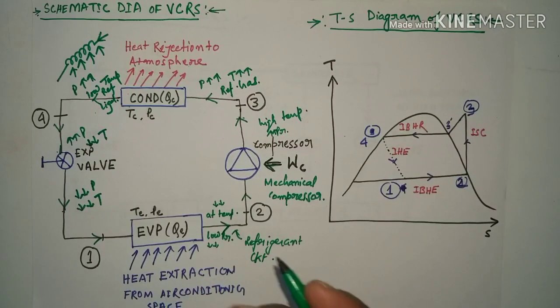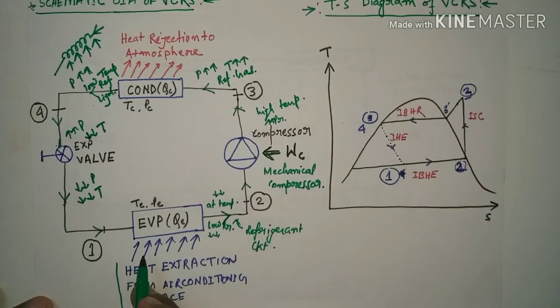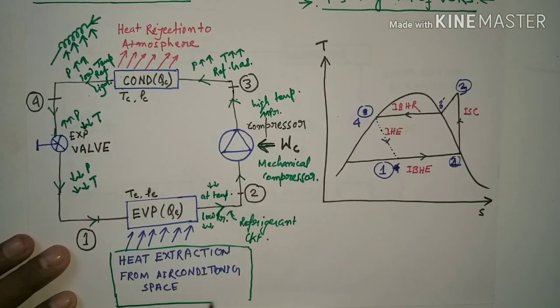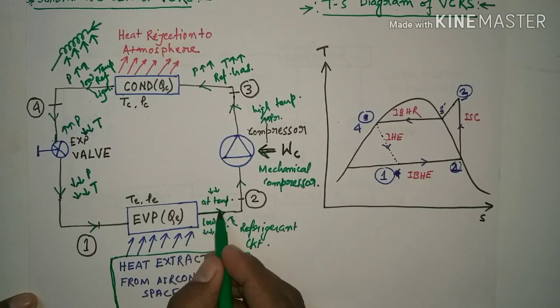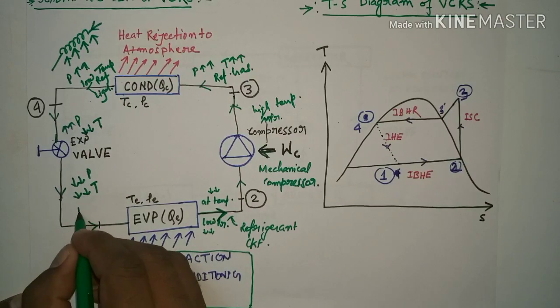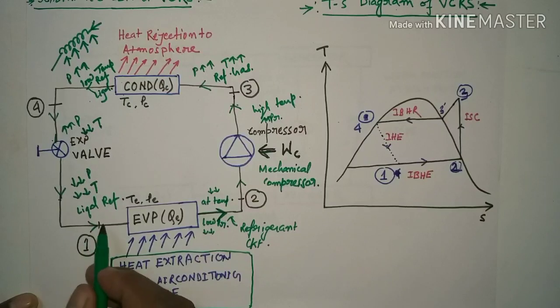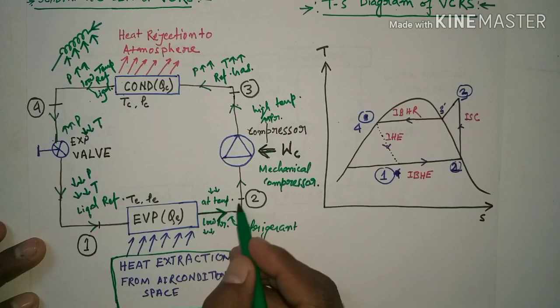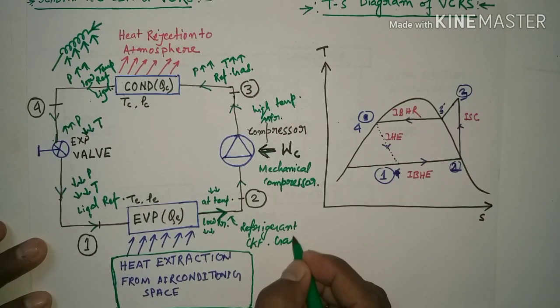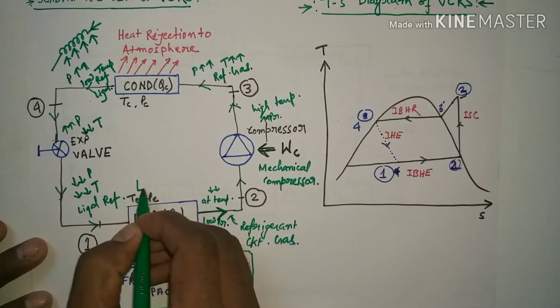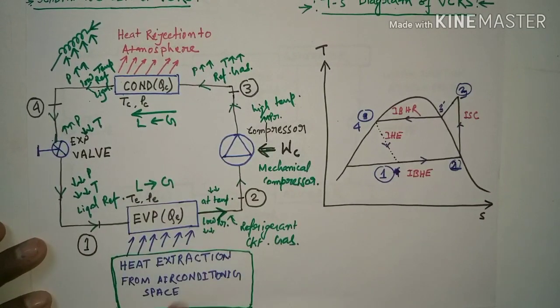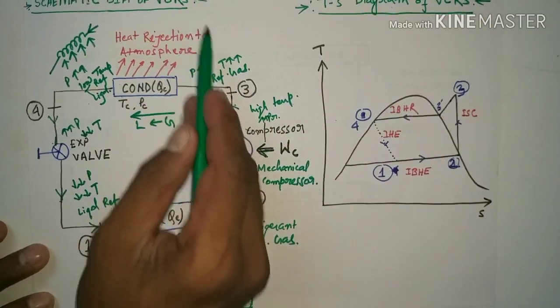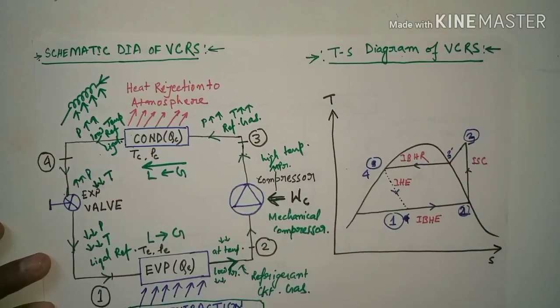After the expansion valve we get low pressure and low temperature refrigerant. When this passes through the evaporator, evaporation occurs. In evaporation, the refrigerant takes heat from the air conditioning space — the space we need to maintain for air conditioning. The low pressure and low temperature liquid refrigerant undergoes a state change in the evaporator from liquid to gas. This entire process is the VCRS — Vapor Compression Refrigeration System.